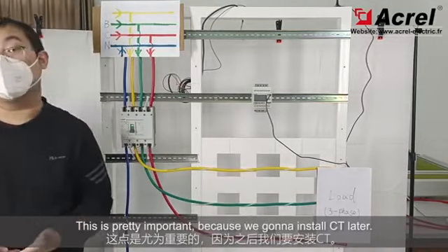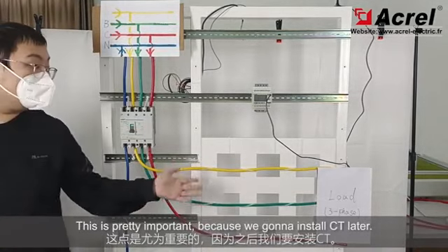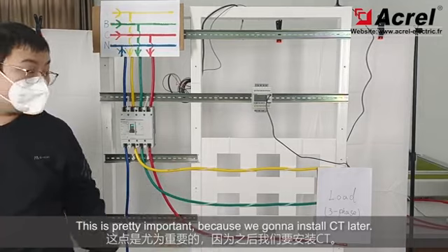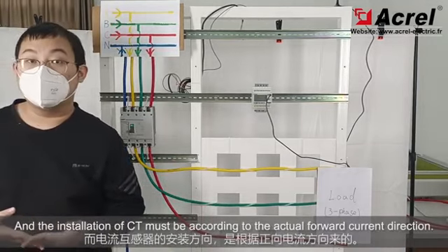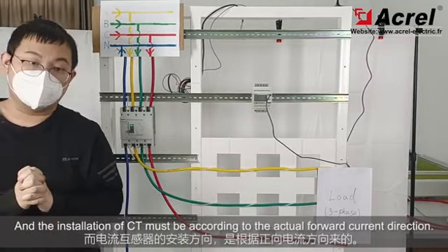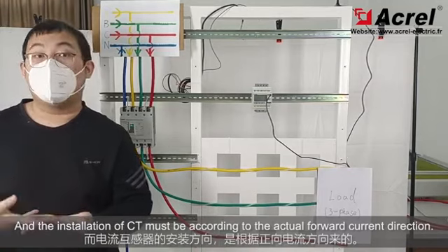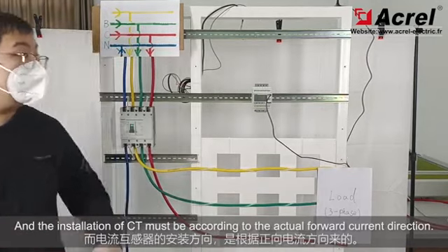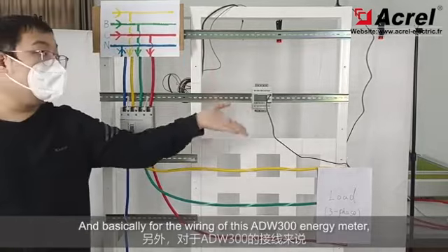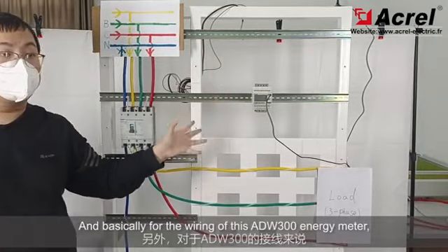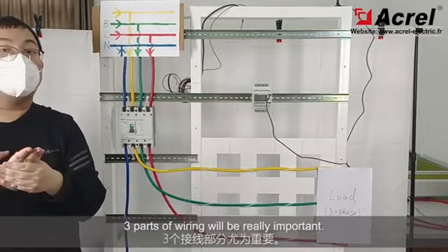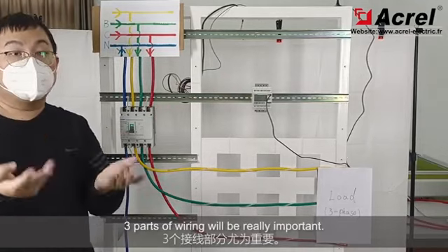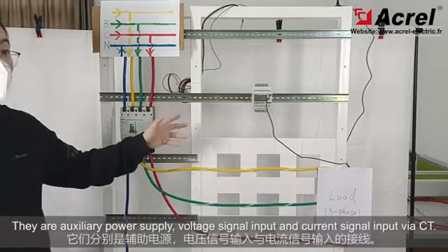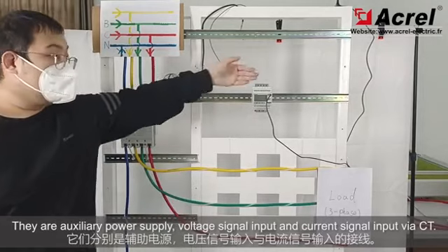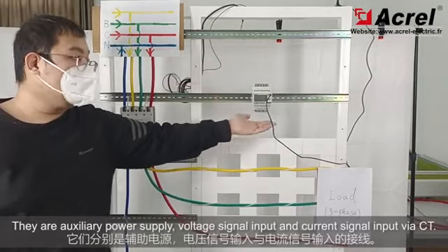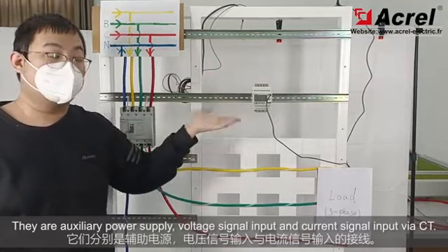This is pretty important because we're going to install the current transformer later, and the installation of the CT must match the actual forward current direction. Basically, for the wiring of this ADW300 energy meter, three parts of wiring are really important: auxiliary power supply, voltage signal input, and current signal input via current transformer.